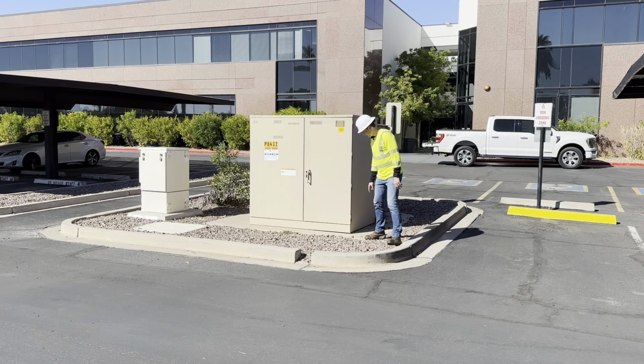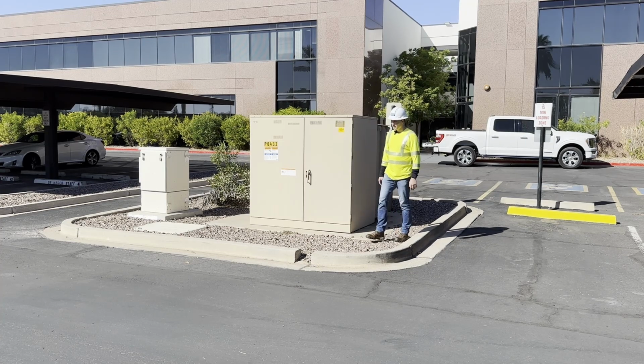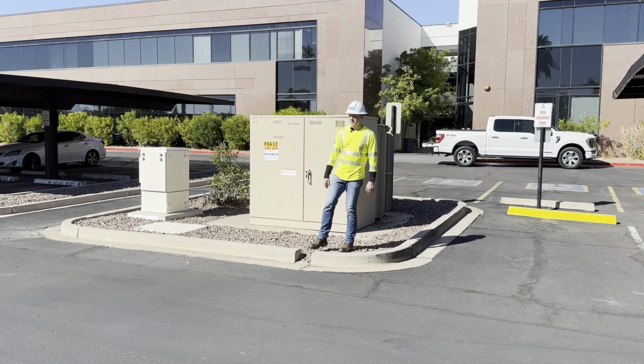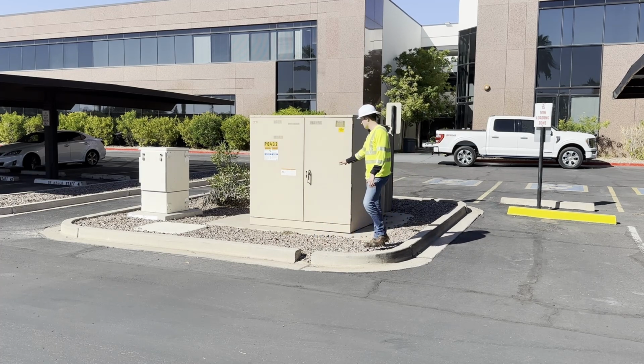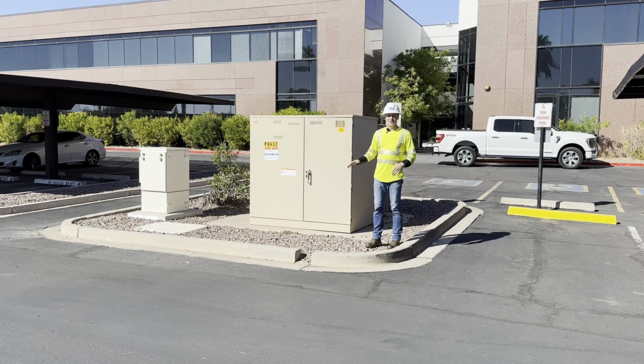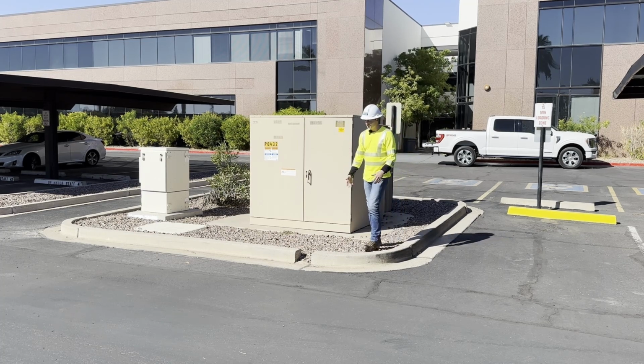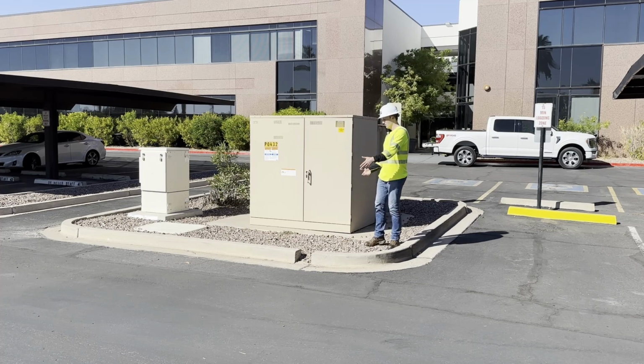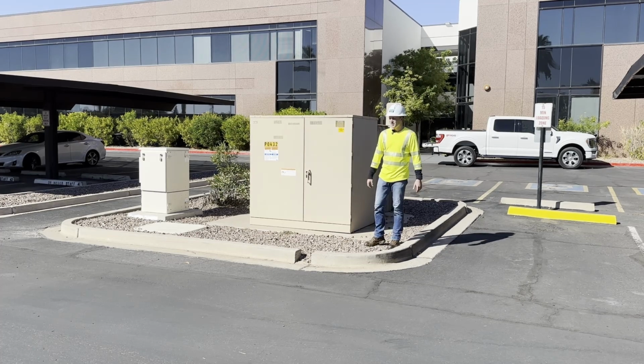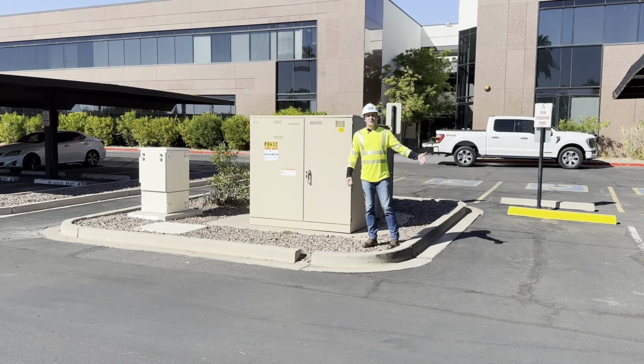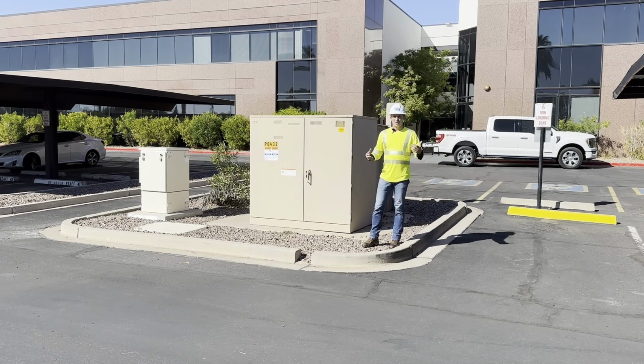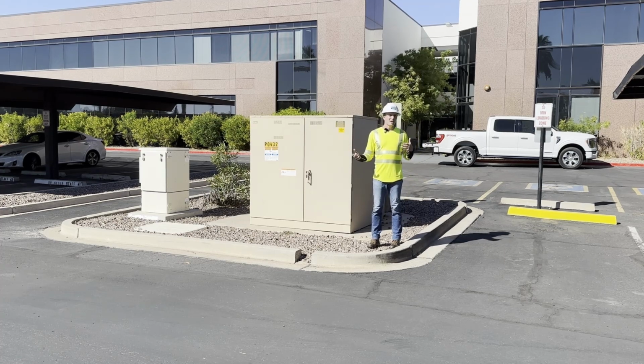Even this pad is actually a little low. I probably would have raised it a foot or two and not put this curb cut here where water can flow in, so the transformer stays isolated during high rain events. This could have been used for drainage too, but given how this parking lot is angled, water is actually going to flow right into this transformer, which isn't ideal. So work with your utility engineer and engineer of record to make sure your transformer is in a safe location not prone to flooding.